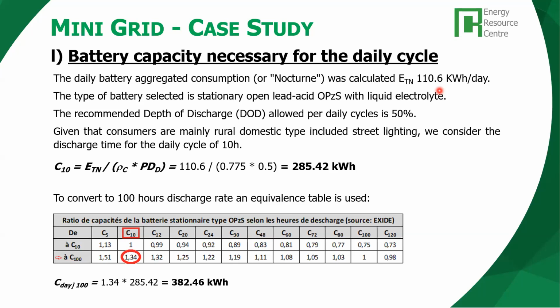Remember, those are the batteries with the highest performance in the family of the lead acid ones. They have some requirements of maintenance, which is to top up with distilled water whenever the level of the liquid electrolyte comes down a little bit after some cycles of operation. The depth of discharge of this type of batteries recommended on a daily cycle is 50%. Remember the presentations we have seen on the battery technologies for lead acid. And given that the customers we have in this mini grid are mainly residential type, also the street lighting, we will have a very intense use cycling of the batteries. So we can consider that batteries will be completing a cycle of charge and discharge every 10 hours.